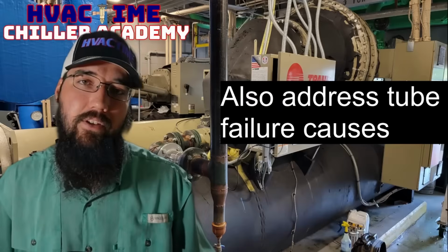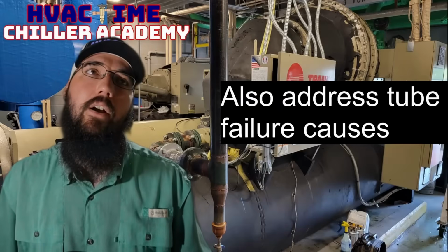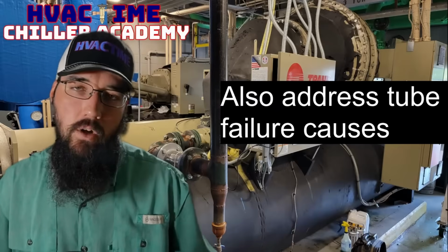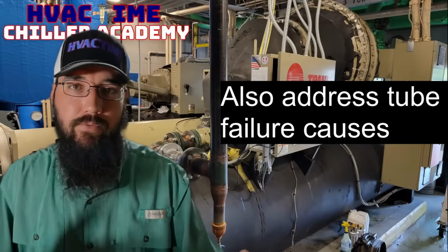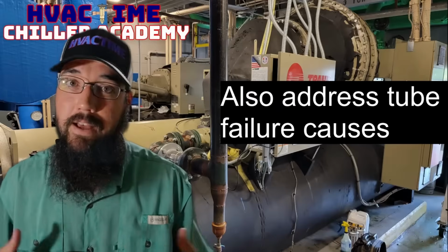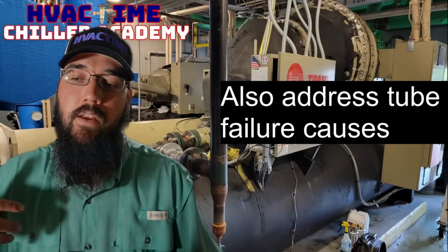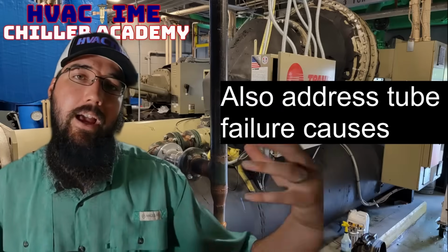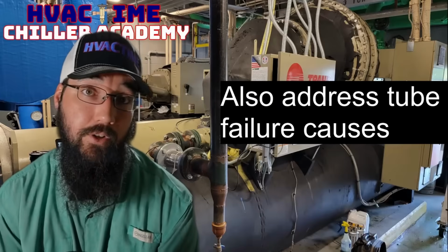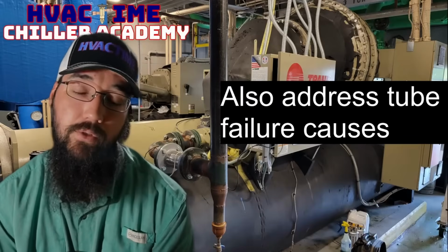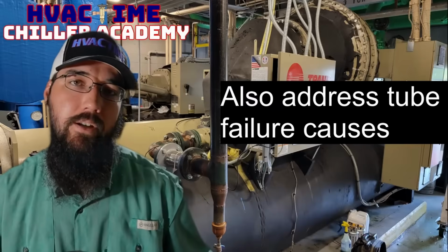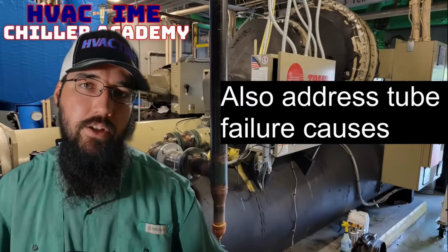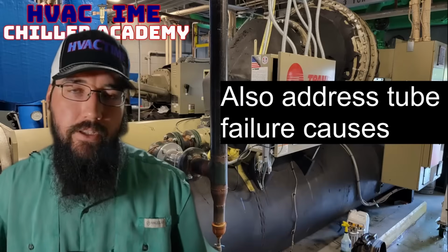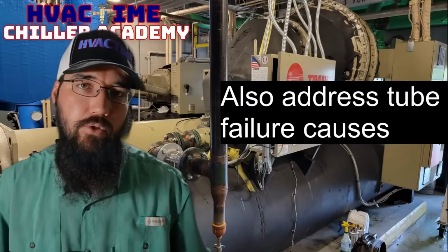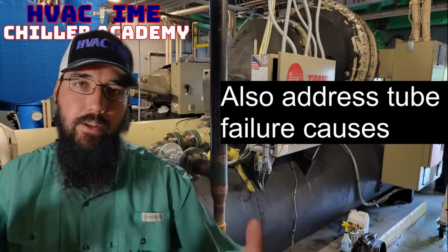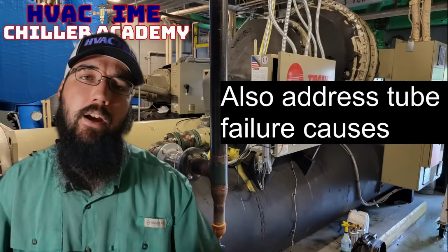One of the saddest ways of having a tube failure is to have the tube freeze. Now, there are two cases where this could happen. One, you could have a genuine freeze at your facility. We actually had this happen in Texas, and it devastated us because we don't have the same winterization that you have in other places. We don't run glycol in our loops. None of our loops are designed for glycol. We typically don't drain our loops, or at least we used to not, because the down period was so short and we had enough insulation that we rarely got cold enough long enough. And usually flowing water was more than adequate to protect our tubes in the wintertime when it got below freezing.